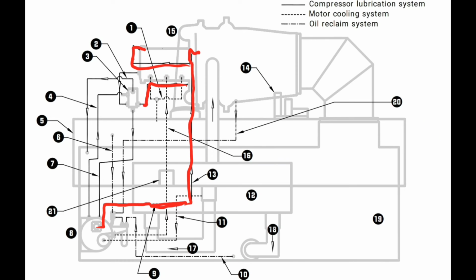This port here is the oil return for the front bearing assembly. This is the oil return for the rear bearing assembly, coming into this little oil separator. Again, the purpose of this is to take any refrigerant that gets trapped in the oil and give it a place to release so that it doesn't make its way into the sump. Some of it will. That's why we have a vent on the tank itself, but we're trying to prevent as much as possible. From there, the oil just gravity feeds down back into the sump, and then back through the pump, and out it goes, whole nine yards. That is the basic makeup of your oil management side of the system.